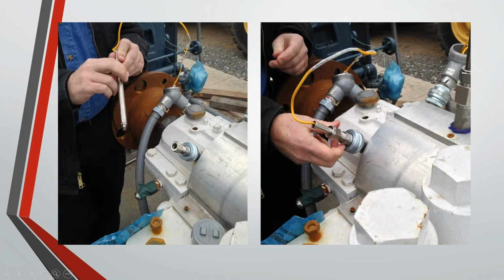We want to get a really close and accurate gap from the probe tip to the shaft, maybe about 50 mils. In order to do that, we're going to have someone go out and gap the probe. In this case, the probe is threaded in backwards into the sleeve. There's a reverse mount probe, and the sleeve then inserts into the shaft holder here, and you tighten it down when you get it exactly where you want it on the machine.